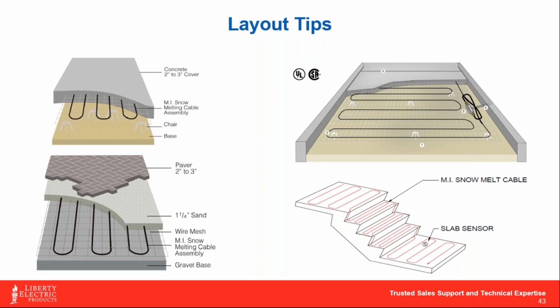When we look at how these products fit within different types of pavement material, we've got 2-part pour applications here, and we can do them with pavers. The big thing with pavers or putting anything like that above it is that you must have at least 1 inch of sand or stone dust covering those cables. You cannot put the weight of those rocks on top of the cables, or else you will break them. They just need to be completely encased in some sort of sand or compactable media.